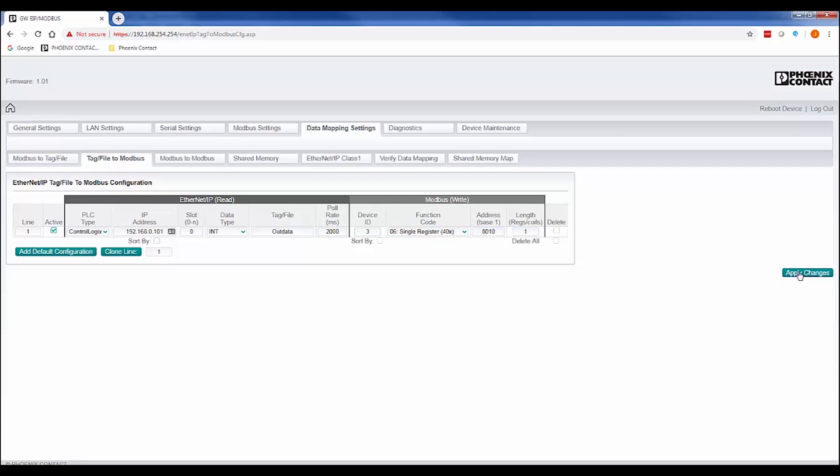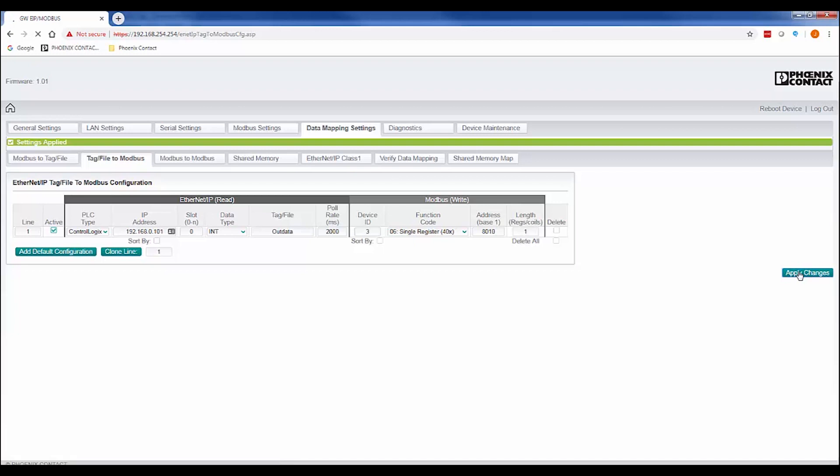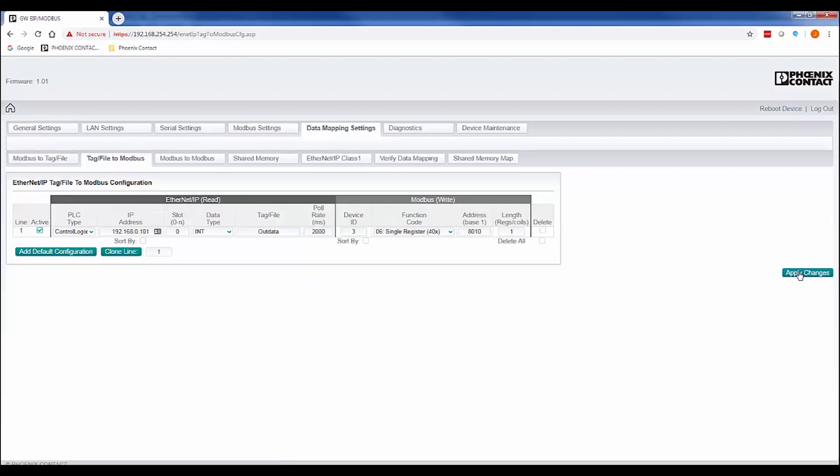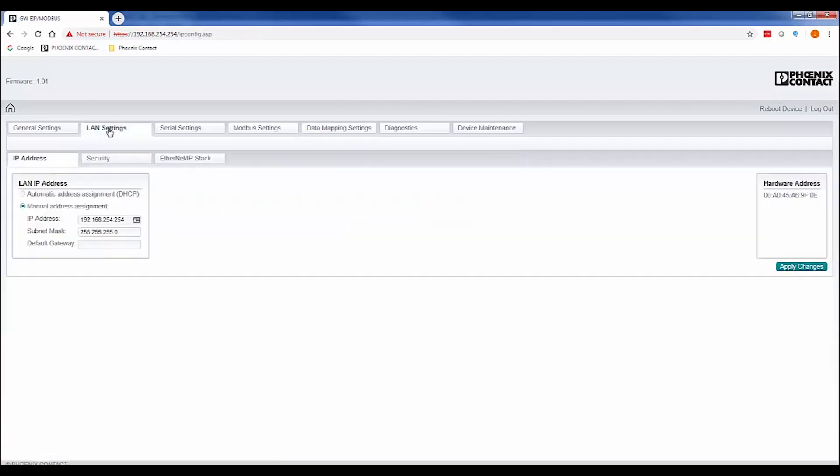The last step is to set the unit's final IP address so it can be accessed from the IP address range our PLC and Modbus TCP device is currently on. This can be done under the LAN setting tab. In the IP address window, enter the desired IP address you want to use and click the Apply Changes button. Once you click the button, the unit will reboot and will be ready to start converting your Modbus data to EtherNet/IP and vice versa.